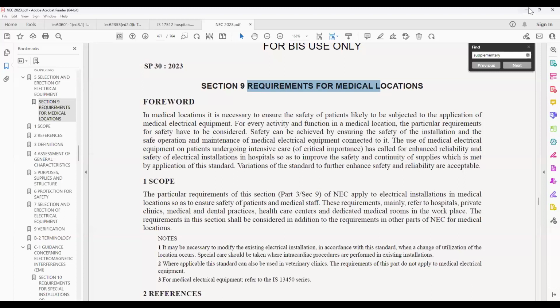The medical locations are classified into group 0, group 1, and group 2. There are 3 types of medical location. Group 0 means a medical location where no applied parts are intended to be used. There are no applied parts used in a group 0 location in a hospital. Group 1 means a medical location where applied parts are intended to be used externally. Group 2 is a medical location where applied parts are intended to be used in applications such as intracardiac procedures, operation theaters, and vital equipment. So basically, depending upon the criticality of the location, there are 3 classifications: Group 0, Group 1, and Group 2 locations.